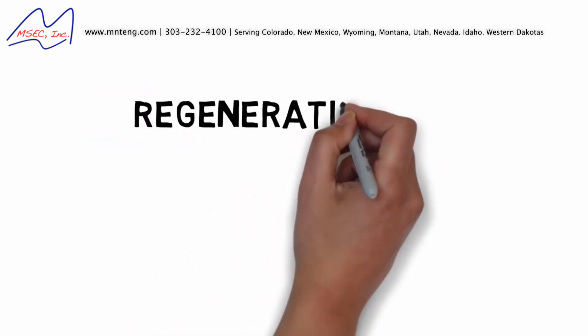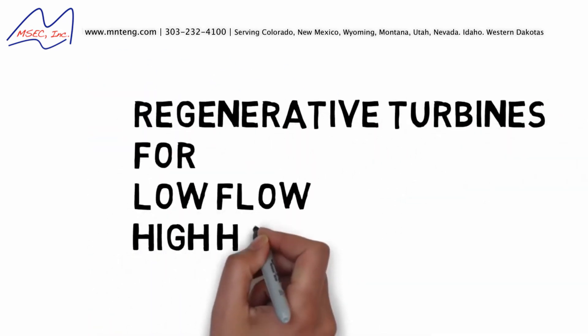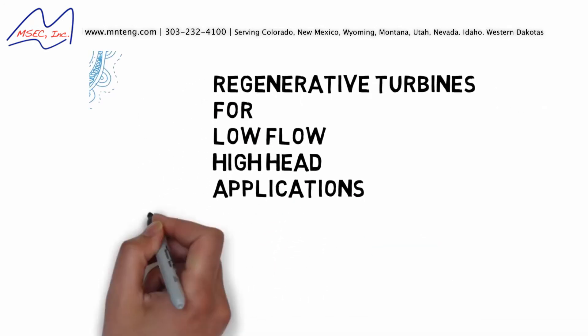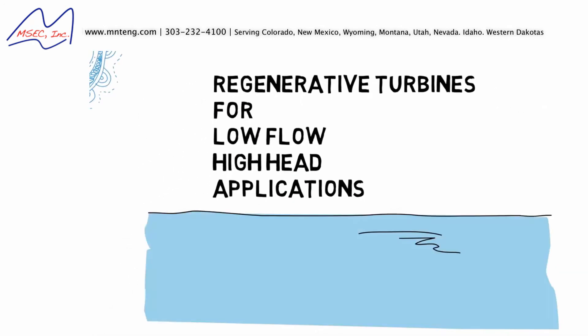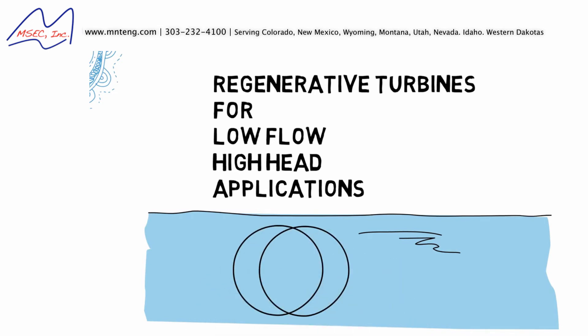For low flow, high head applications, regenerative turbine pumps offer better efficiency than centrifugal pumps and can develop several times the discharge pressure of a centrifugal pump having an equally sized impeller.